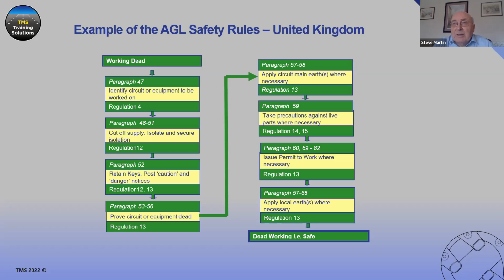Doing that with AGL is quite difficult, because all the equipment is mainly designed for installation out in the field and made waterproof to prevent water ingress, so getting access is difficult. Usually the only point we can do that, as Keith highlighted, is the output disconnecting device on the output of the CCR. Once we've isolated the circuit we can usually get to that point and put a tester in there.